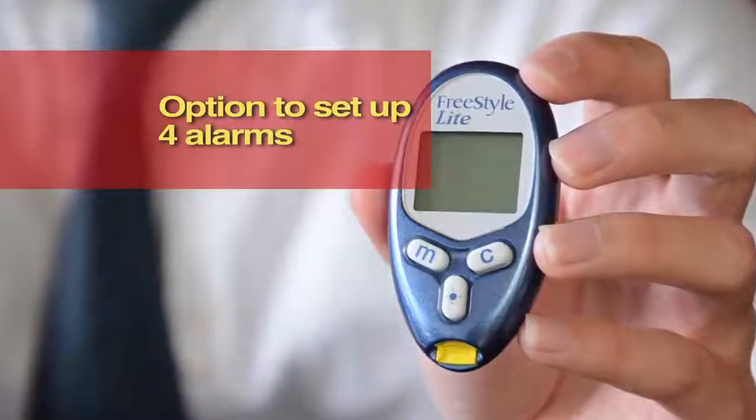This would be convenient for someone who does not bleed very well or if someone has taken the blood sample away from the test strip too early. And it's also cost effective because you do not have to discard that test strip and start with a new one. There's an option to set up to four alarms. This function would be handy for someone who is testing their blood glucose several times each day, and it's ideal for someone who is injecting insulin several times each day. It's also a great reminder for someone who is very busy or has difficulty remembering to test their blood glucose, or someone who takes their medications around testing time.